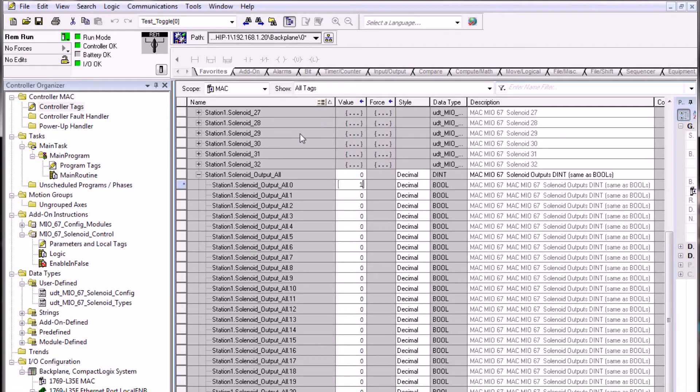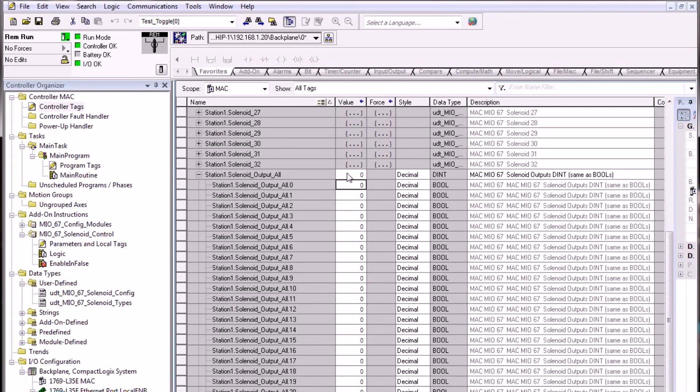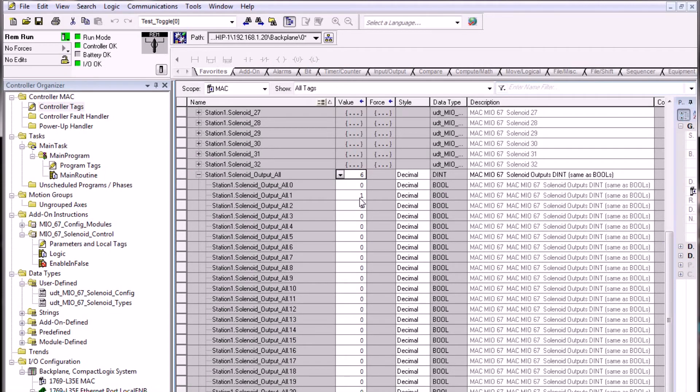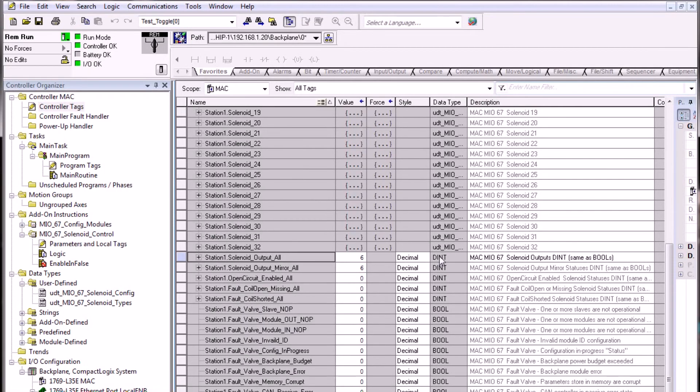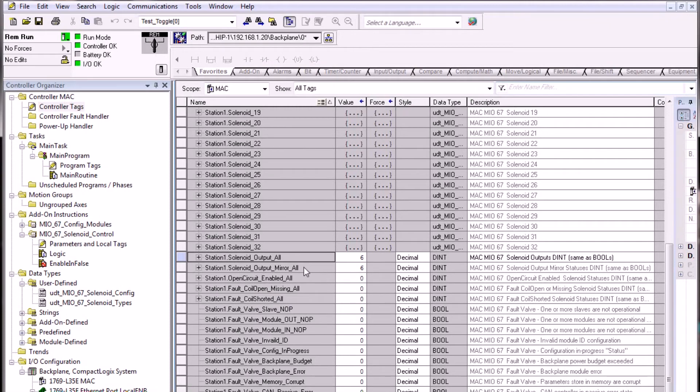If we write a 1 into this bit, we turn that solenoid 1 on. We can also turn multiple solenoids on by writing an integer value into the integer of solenoid output all. This turns on two outputs simultaneously because this is the binary representation of 6 in boolean down below. By utilizing the double int value, we can see the status of the output equals 6 and the output mirror equals 6. This indicates that the valve is operating properly when it echoes the mirror output.